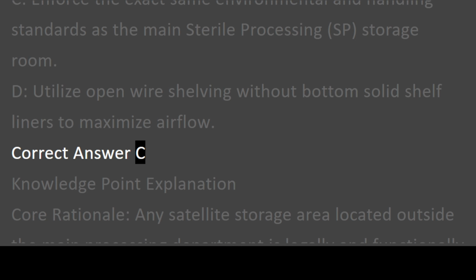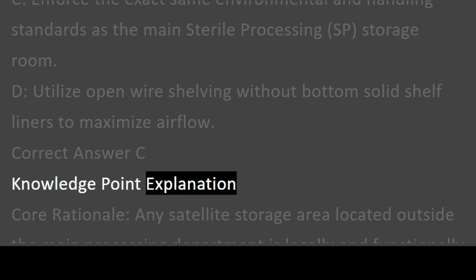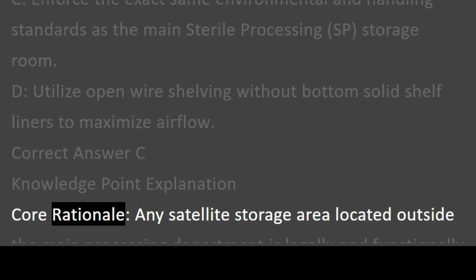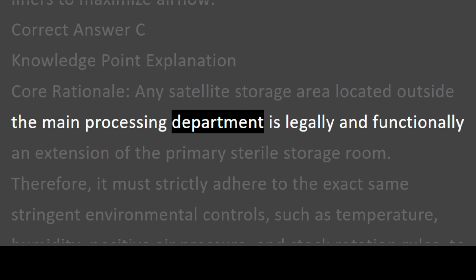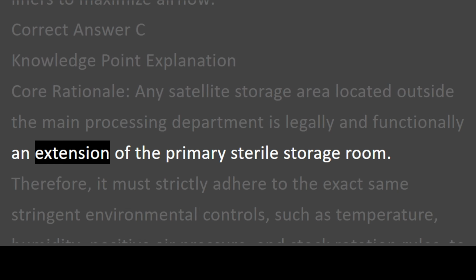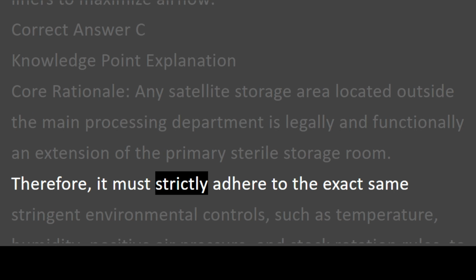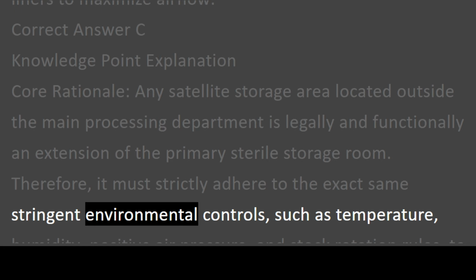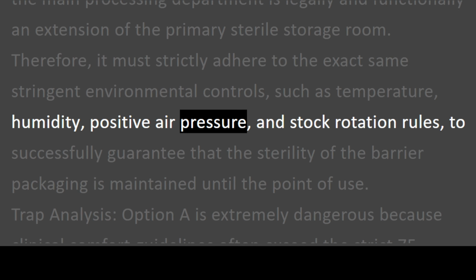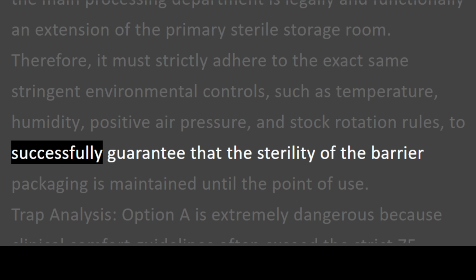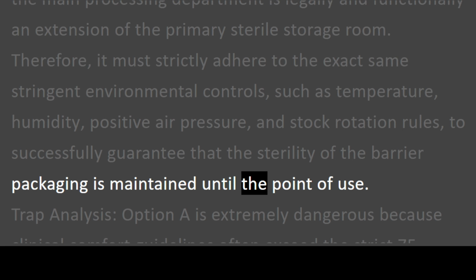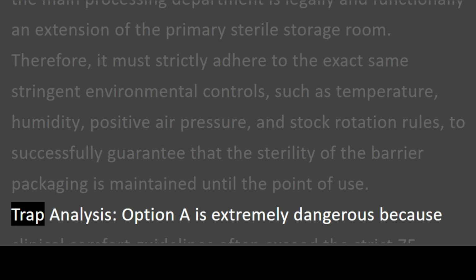Correct answer C. Knowledge point explanation. Core rationale. Any satellite storage area located outside the main processing department is legally and functionally an extension of the primary sterile storage room. Therefore, it must strictly adhere to the exact same stringent environmental controls, such as temperature, humidity, positive air pressure, and stock rotation rules, to successfully guarantee that the sterility of the barrier packaging is maintained until the point of use. Trap analysis.